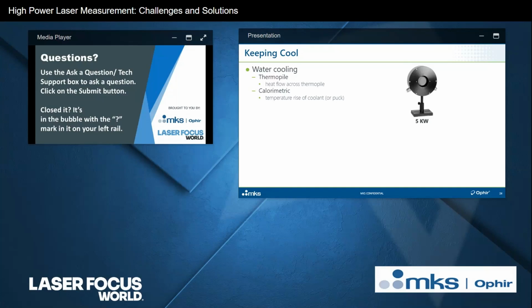There's another type of water-cooled sensor, and that operates on a similar but not exactly identical principle, and those are what we call calorimetric sensors. Calorimetric sensors, by that I mean that the cooling water not only removes heat, but it's actually part of the measurement process itself. We're going to talk about that in a touch more detail in about a minute. But before we do that, there are a few important pointers about the cooling water that I want to mention. And by the way, remember this calorimetric thing, because we're going to be coming back to this also shortly.